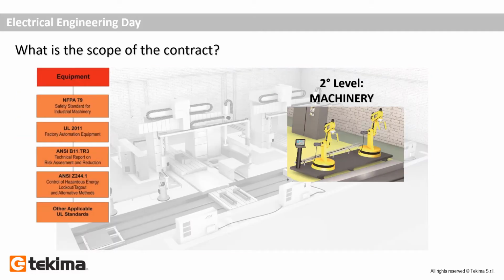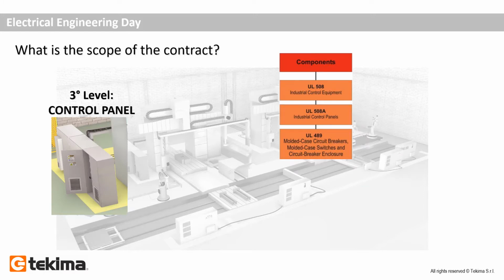Second level, equipment. The most important document to consider for this level, which is most closely related to our job, since it concerns machinery, is ANSI NFPA 79 industrial machinery. Last level, control panels. In this case, the master document to consider is ANSI UL 508A industrial control panels.